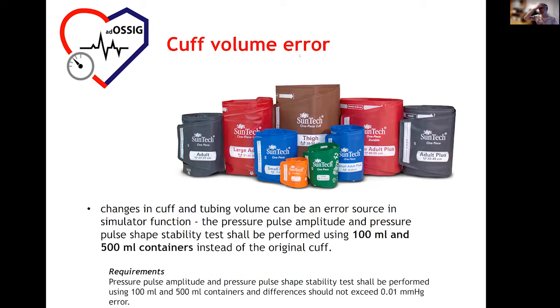The cuff volume, why actually the cuff volume? You have to have in mind that the home blood pressure monitors usually come with one cuff, sometimes two. But usually a lot of different sizes of cuffs could be connected to the blood pressure monitors. And here, this orange one is for neonates, for really small kids, and then larger and larger for adults. And the thing is, sometimes the monitors themselves are tested clinically using more devices, because you have to have in mind, if you have a single cuff which has its own volume, and then the tubing, a device having a small cuff and the same device having larger cuffs could be regarded as two different devices.